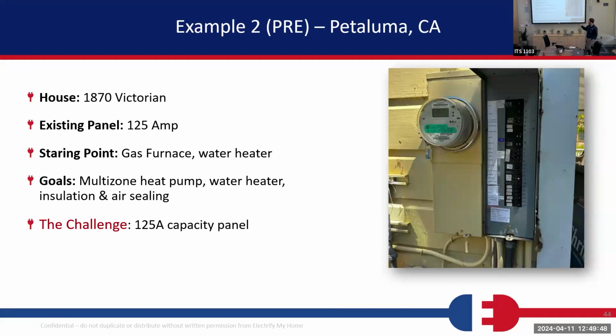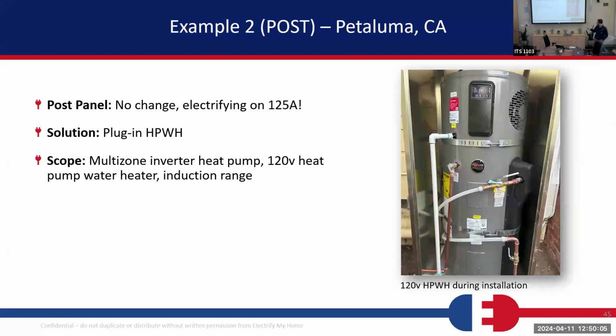Okay, another one: 125 amps in Petaluma, really old house, gas furnace, gas water heater. We ended up putting a multi-zone heat pump with wall mounts. We don't do too many of those, but it was the right choice in this decision. Water heater installation and air sealing. So really the panel we left the same, but we put in a plug-in heat pump water heater to enable us to meet the NEC load count for this scenario, because you would have been over 125 amps.